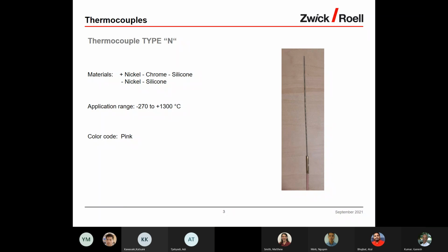The first thermocouple, type N. The material on the plus side: nickel, chrome, silicon. On the minus side: nickel and silicon. Application range from -270 to +1300 degrees. And the color code is pink.